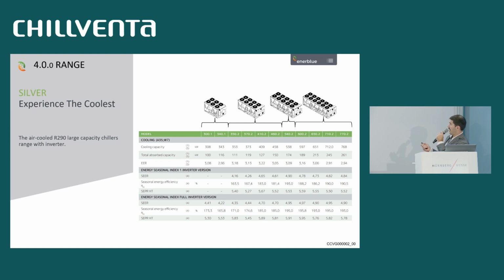These are the 11 sizes of the range, which goes between 300 kW cooling capacity up to 770 kW at air temperature 35, water 7. The level of efficiency of the unit is impressive. With one inverter compressor and one on-off compressor, we have more or less 4.6, 4.9, so relatively good levels of efficiency. If we consider a full inverter version, so 2 inverter-driven compressors, we have an even higher level of efficiency.